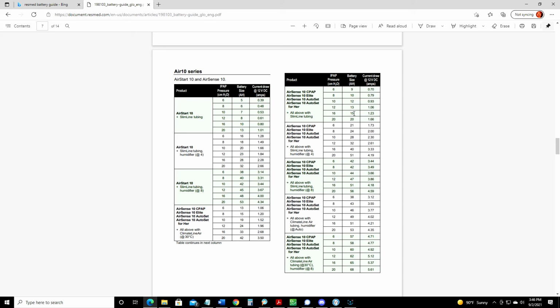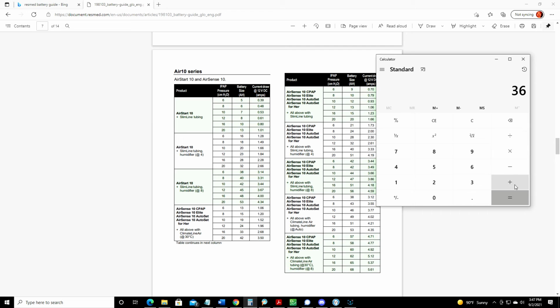But of course, I used a humidifier level of 6, which complicates things a little bit because we're going to have to do 2 averages here. I'm between 4 and 8, and I'm also in pressure sort of between 12 and 16. Let's just call it 14, which would be toward the upper end of my pressure range, but still that's fine. So with the humidifier set at 4, I would need somewhere between 32 and 40 amp hours. So let's just say 36. With humidifier level at 8, I would need somewhere between 49 and 51. So let's say 50. So 36 plus 50 divided by 2.